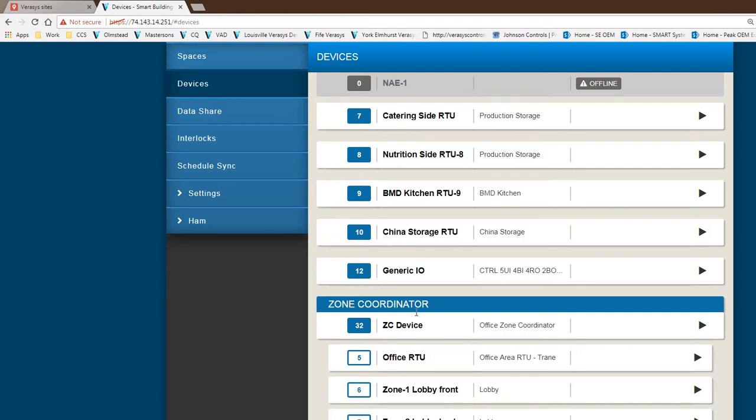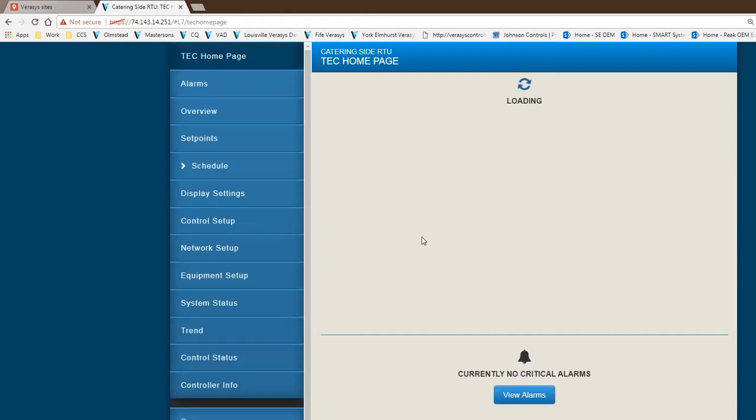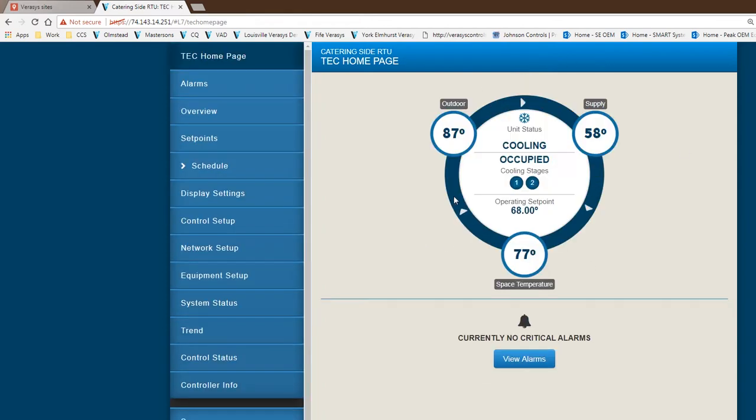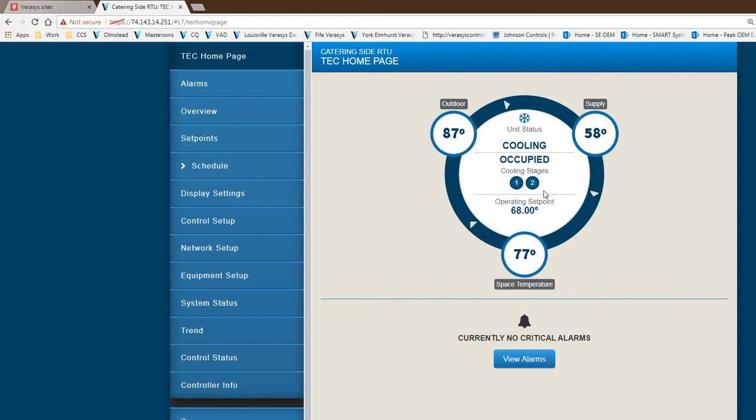The device list gives you information to go into detail for a particular piece of equipment. If I click on a single zone rooftop, you get what we call the circle home screen. In this case it's showing cooling with two stages of cooling on 58 degrees supply, trying to maintain the set point needed.